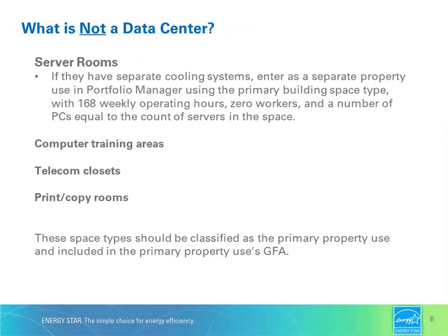Especially when you're dealing with smaller spaces within a larger office building, it's important to be very specific about whether the space meets the definition of a data center or not for purposes of Energy Star benchmarking. A server room may share some features with a true data center, but if it's just a server closet, or if its constant power load is significantly lower than 75 kilowatts, or if there's no dedicated cooling or no UPS, then it's probably not a true data center.